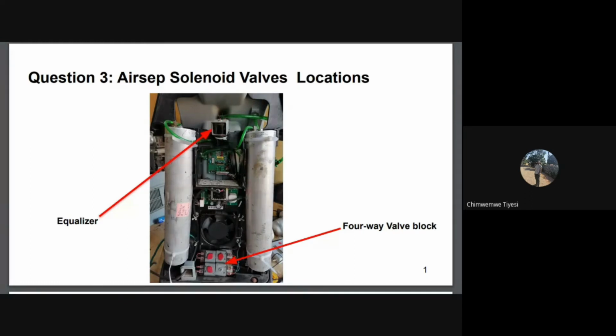So what might happen when you replace the valve block coil with the equalizer coil? The equalizer coil now on the valve block will heat up more than the other valves on the valve block, and eventually will start to underperform and affect the performance of the concentrator after running for some time. So it is good practice to always replace parts with the original or required spare parts, as that will not affect the performance in the long run. Thank you, Maui.